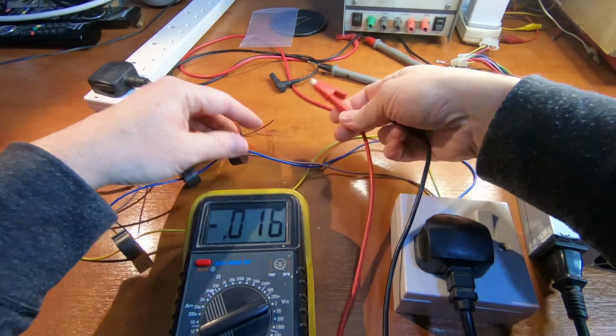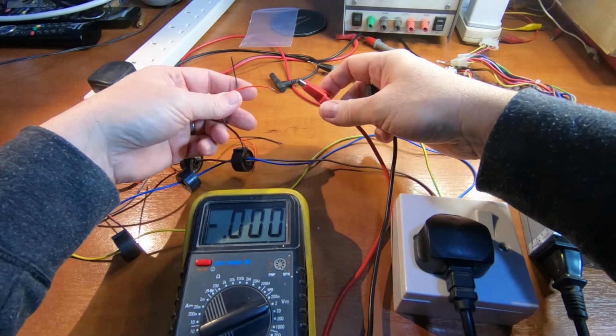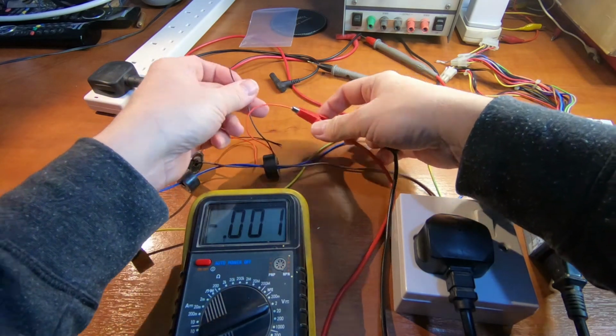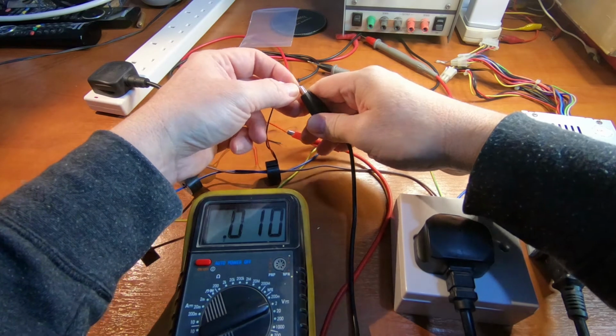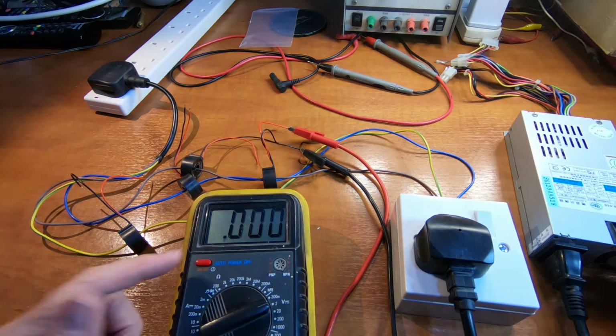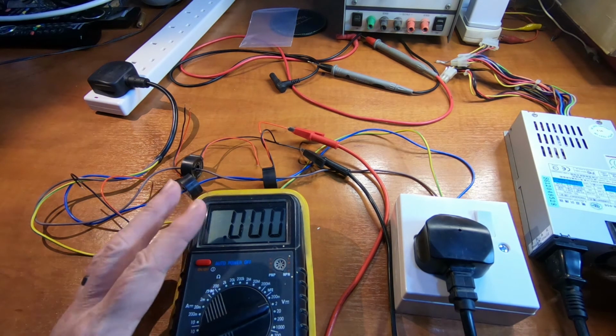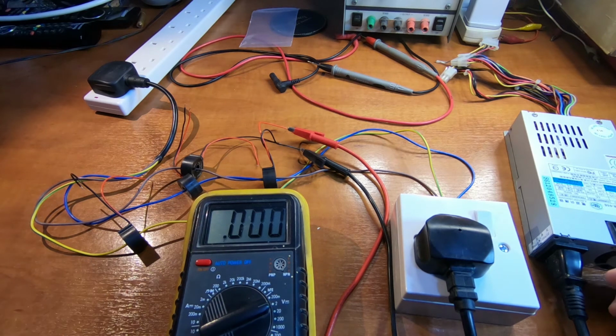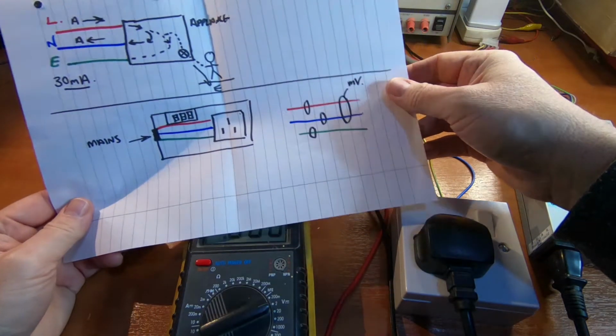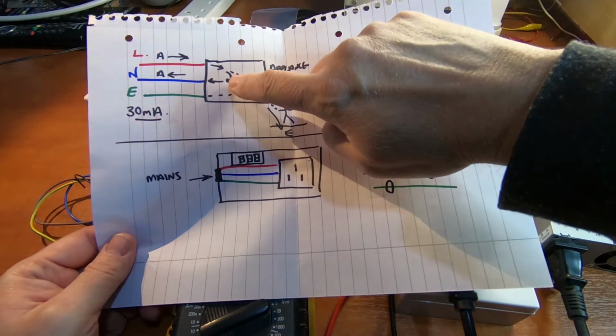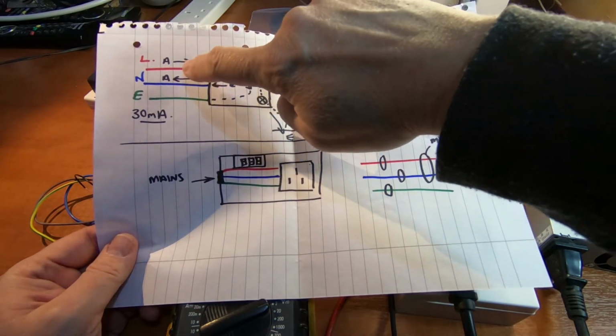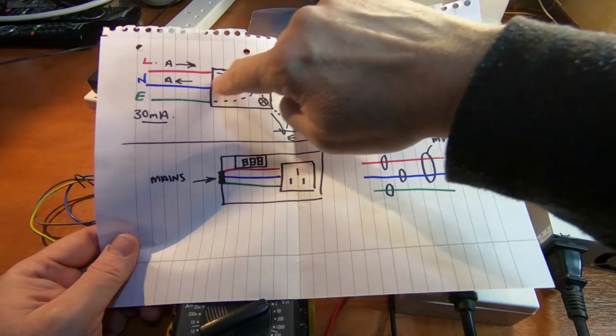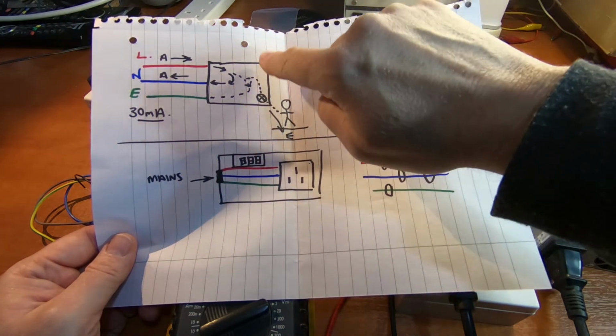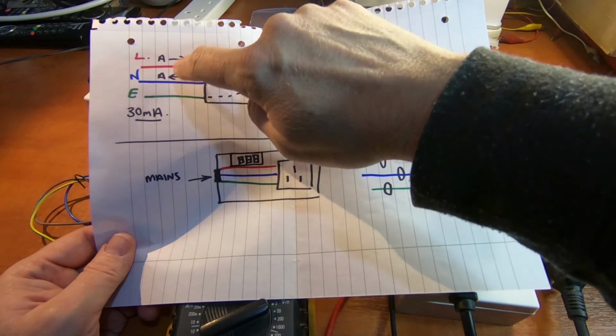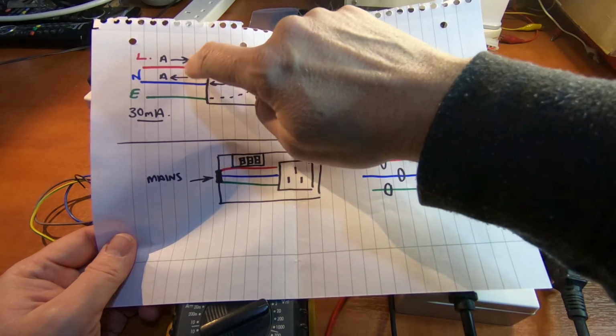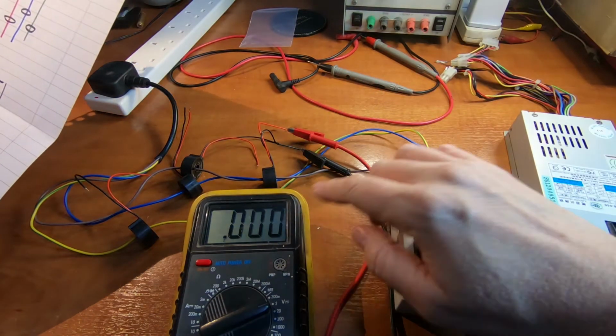Disconnect that, and we'll go on to the combined current transformer. Yeah, 0. So in a working appliance, this is what I'd expect - the input current is going straight in and straight out, so it's a closed loop. This earth leakage isn't taking place, so the difference between these, or the current drawn overall between these conductors, is coming back as 0.